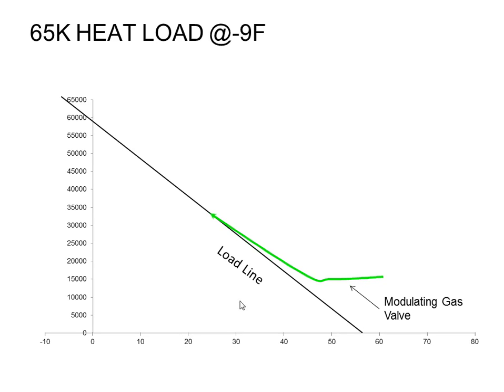They ramp their modulating furnace capacity up the line, and then at some point they satisfy the thermostat, and then they shut the furnace off, and then they wait for the house to cool a degree or whatever it is to kick the thermostat back on, and then they turn the furnace on and then ramp it up again. The Bryant one and the Carrier one are going to actually be able to ramp back down. So we're never actually going to cycle off. We're just going to ramp up and down, up and down, up and down, continuously flowing gas.